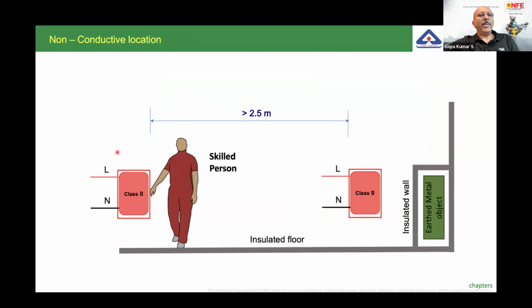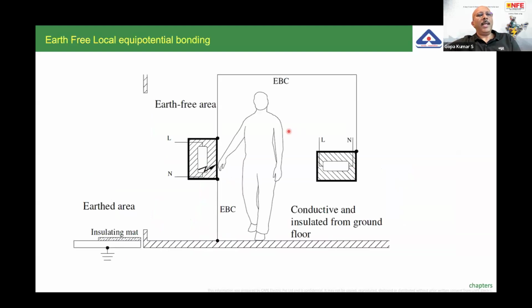Similarly, the other safety measure which can be applied is non-conductive location. Non-conductive location means you have class 0 equipment. Class 0 equipment means the live parts are exposed, and the operating voltage shall be lesser than 150 volt AC. You can look at the standard. So there are locations where sometimes the live parts are exposed, meaning the equipment are class 0 equipment. Skilled people can work in this particular environment, but the entire location is insulated. The complete location is insulated, which is technically called a non-conductive location. So between two class 0 equipment, you have to have 2.5 meters. Simultaneously, a person should not touch both these parts. If somebody touches both these equipment, probably he gets a shock. Similarly, earth-free local equipotential bonding is also a safety measure, meaning there is no metallic object in this particular case.